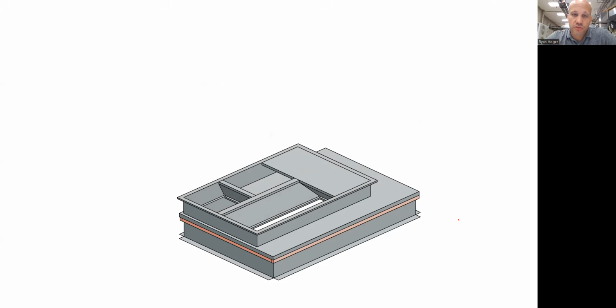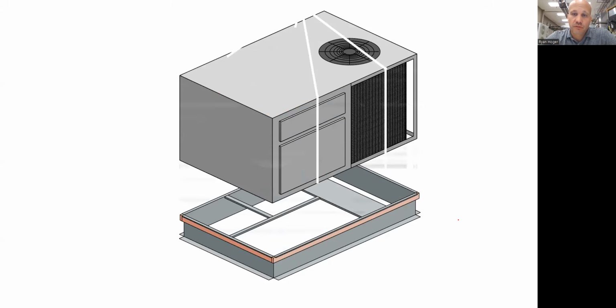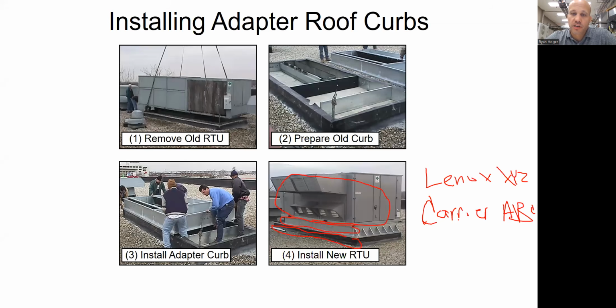We mentioned also, when you're in this scenario here, I said you need to know the old unit and the new unit. Sometimes you'll go to a job site and it already has an adapter on there, right? So the building was built, there was a curb and a rooftop. Let's just say it was an old Carrier unit that was on the curb. And then 20 years later, that thing got replaced with a Lennox unit and they put a curb adapter on it.